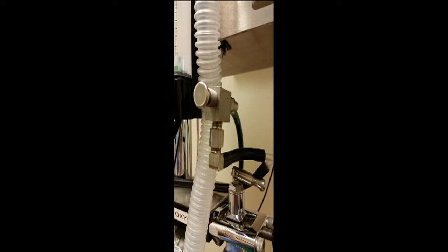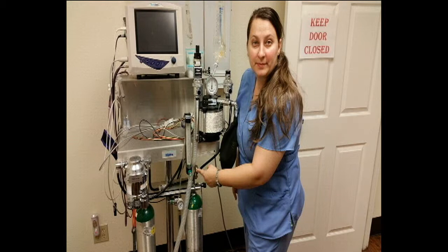Oxygen flush valve bypasses the flow meter and vaporizer to deliver short, large bursts of oxygen into the circuit at a 40 to 70 liters per minute rate. It is used to fill the reservoir bag with pure oxygen and also to deliver fresh pure oxygen into the system. It can also be used to dilute the concentration of anesthetic agent that still remains in the circuit at the end of anesthesia. The oxygen flush valve should not be used when the circuit is connected to our patient. It can cause trauma to the lungs of our patient.